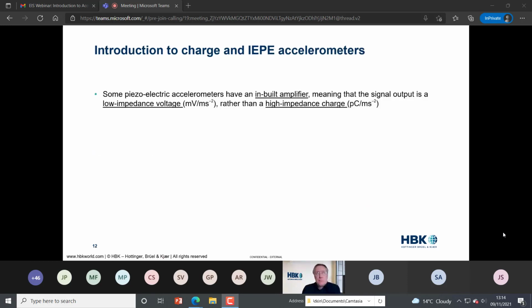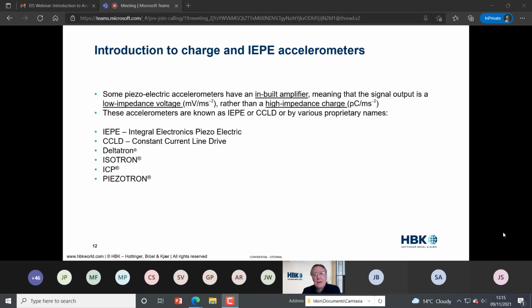Okay, now some piezoelectric accelerometers have an amplifier built into them. And when there is an amplifier in there, we refer to them as IEPE. And when we put an amplifier in, rather than seeing a charge output in terms of picocoulombs per meter per second squared or picocoulombs per G, we see a low impedance voltage output in millivolts per meter per second squared or millivolts per G. And it's the low impedance part that is important. These are known as IEPE or sometimes CCLD, and there are many additional names for this sort of accelerometer, as you can see listed there.